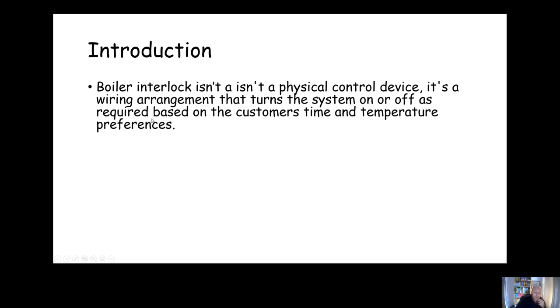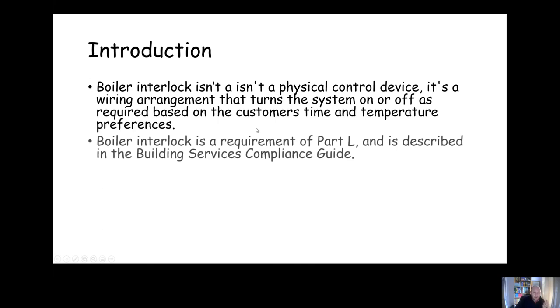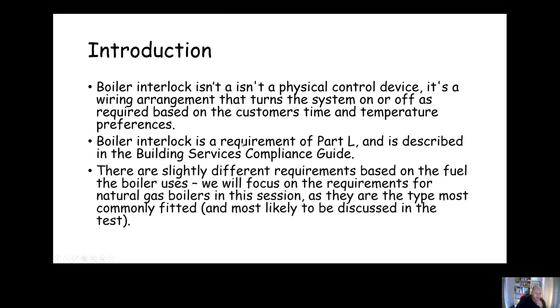So firstly, what is boiler interlock? It isn't actually any one thing. It's a number of things coming together, all wired up together, that will turn the system on or off in an efficient way based on the customer's time and temperature preferences. It's a requirement of Building Regulations Part L, and it's described in the Building Services Compliance Guide.